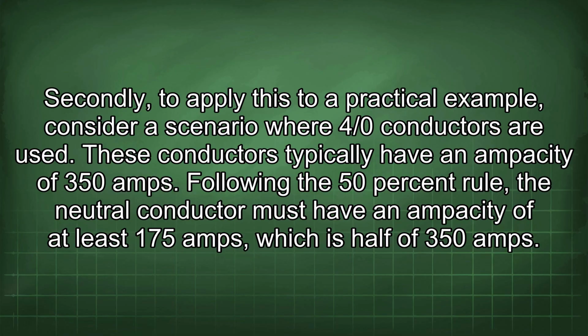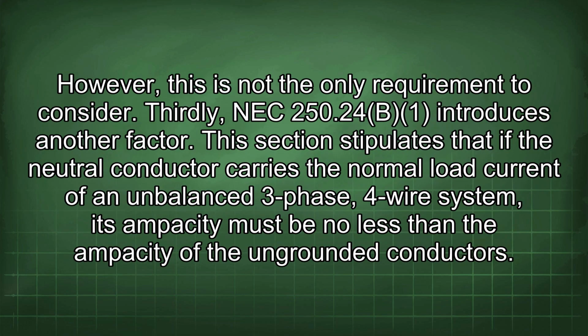These conductors typically have an ampacity of 350 amps. Following the 50% rule, the neutral conductor must have an ampacity of at least 175 amps, which is half of 350 amps. However, this is not the only requirement to consider. Thirdly, NEC 250.24(B) introduces another factor.